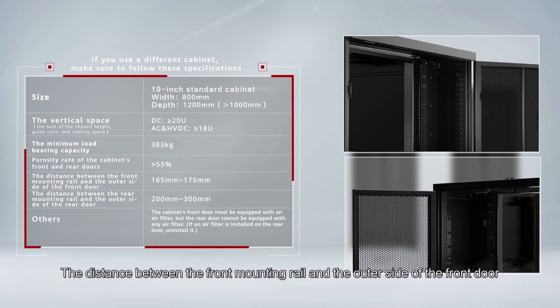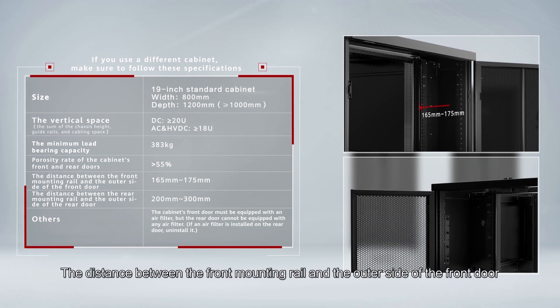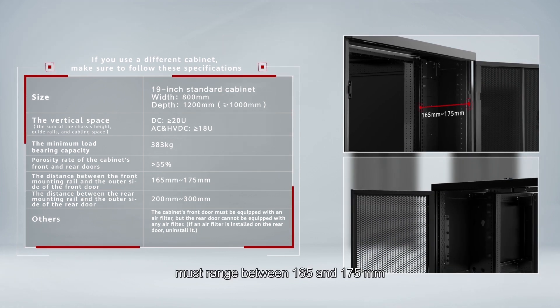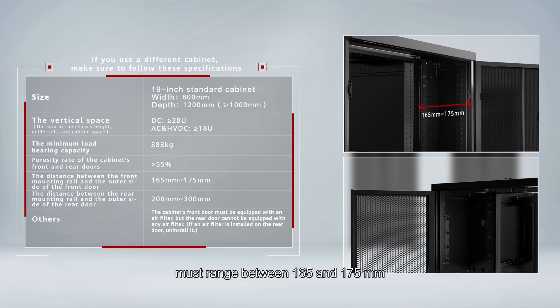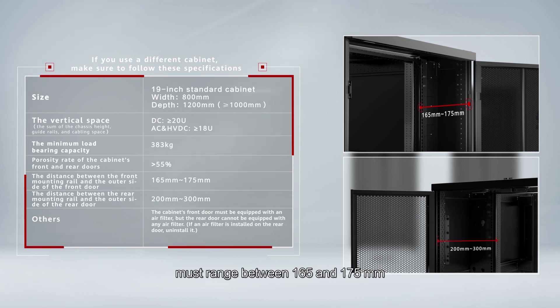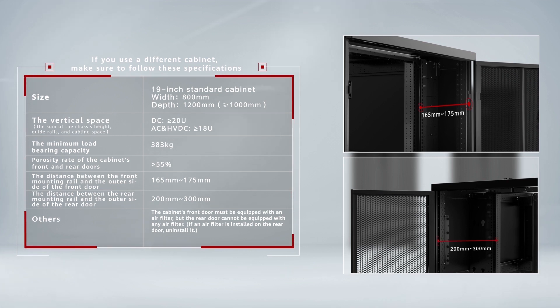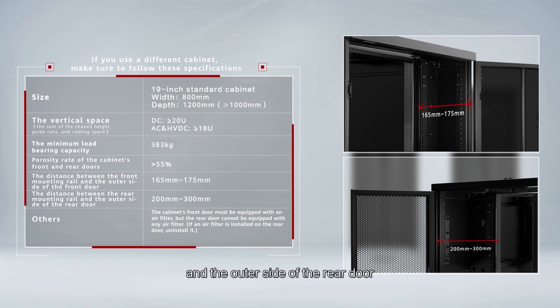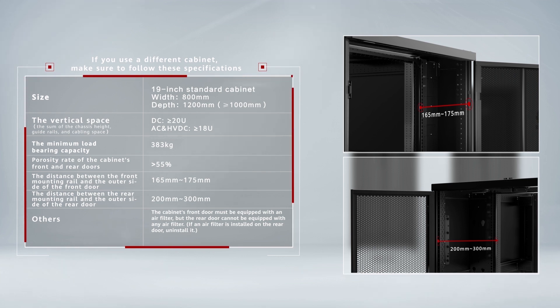The distance between the front mounting rail and the outer side of the front door must range between 165 and 175 millimeters. The distance between the rear mounting rail and the outer side of the rear door must range between 200 and 300 millimeters.